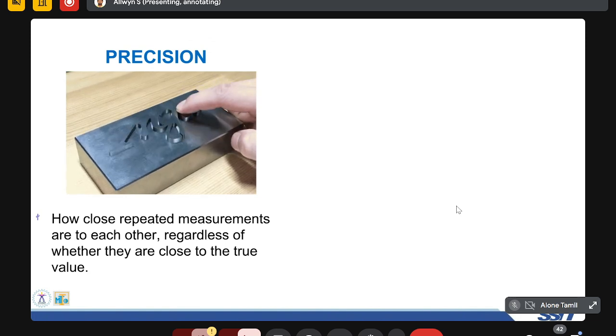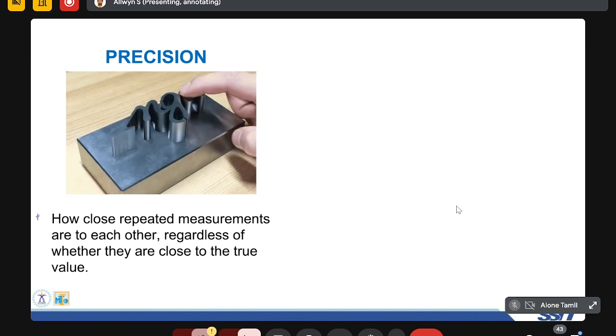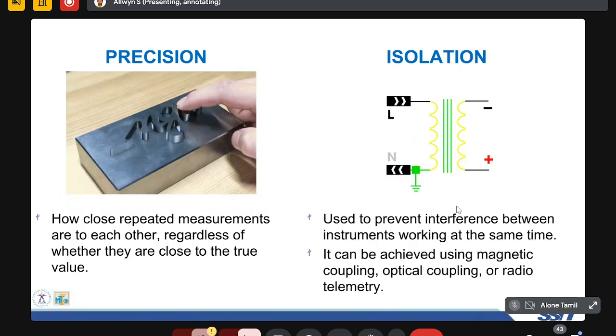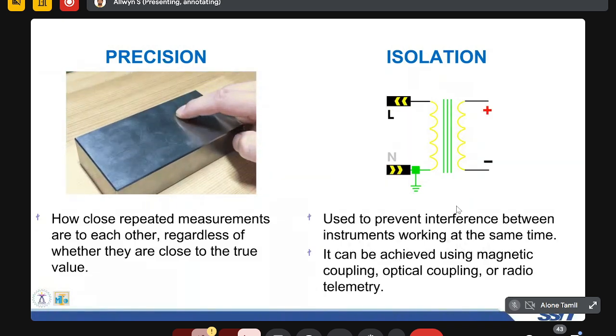And the precision. Precision refers to the degree of refinement of a measurement, the number of distinguishable alternatives from which the given result is measured. For example, the value on the device shows 2.434 or 2.43; such precision should be there in an equipment. It shows how close repeated measurements are to each other. That is the precision of the instrument. The next one is isolation. For any biomedical equipment, isolation is necessary in order to avoid any micro or macro shock. It is used to prevent interference between the instrument working at the same time from the patient as well as the equipment.